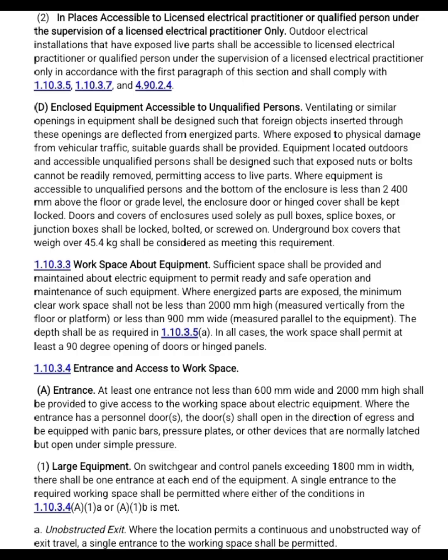Where equipment is accessible to unqualified persons and the bottom of the enclosure is less than 2,400 mm above the floor or grade level, the enclosure door or hinge cover shall be kept locked. Doors and covers for enclosures used solely as pull boxes, splice boxes, or junction boxes shall be locked, bolted, or screwed on. Underground box covers that weigh over 45.4 kg shall be considered as meeting this requirement.